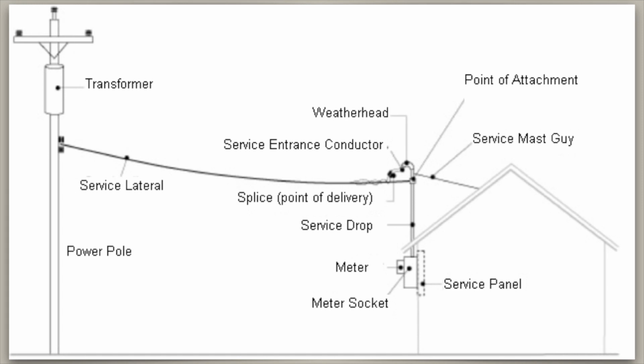If the service lateral is carried along overhead cables, the service lateral to the house is a triplex cable. Usually, two 120-volt black or hot wires and a third white or neutral wire that is insulated and usually twisted around a metal cable, which is sometimes used as the main ground. Typically, 200 to 240 volts of alternating current, or AC, is supplied to residential dwellings on two separate lines of 110 volts each. The AC can change from 0 to over 110 volts and then to less than 110 volts and back 60 times per second. With that, the service is described as 110-volt alternating current at 60 Hz.